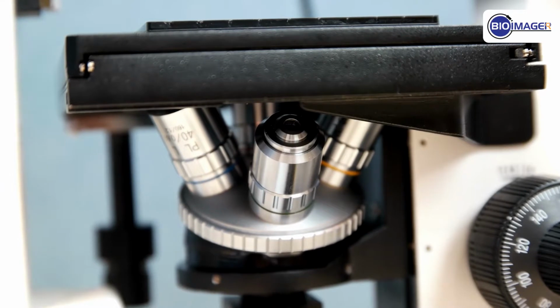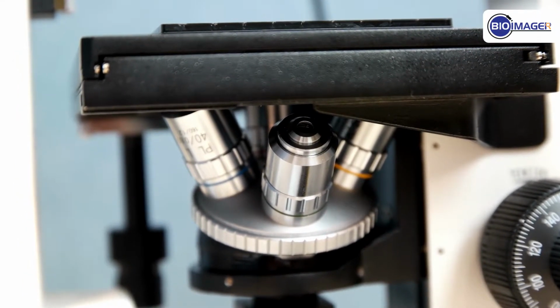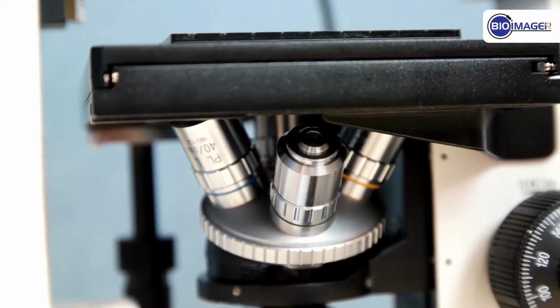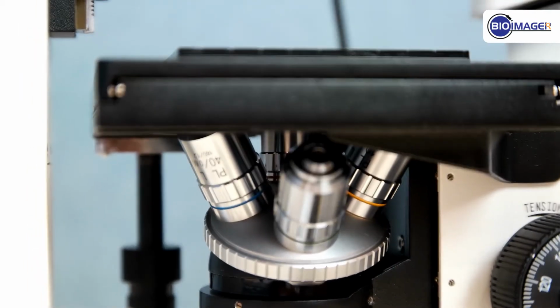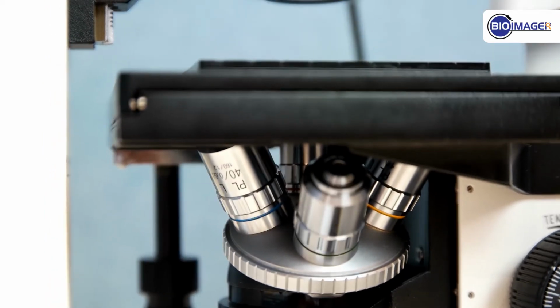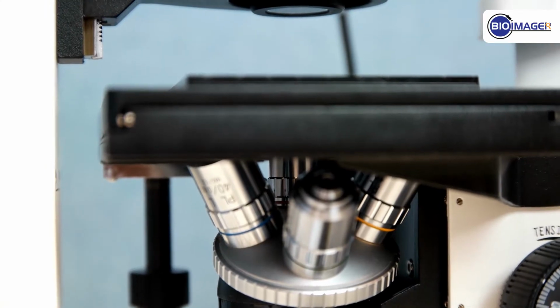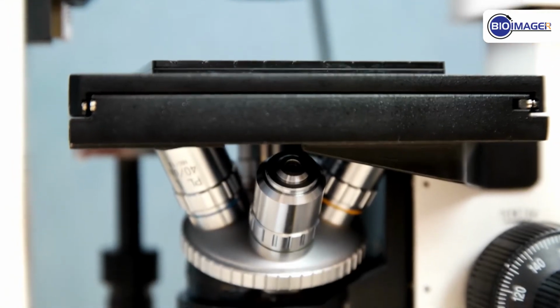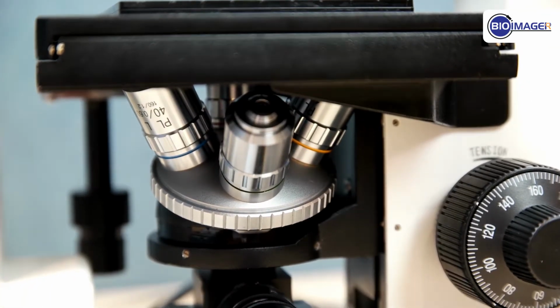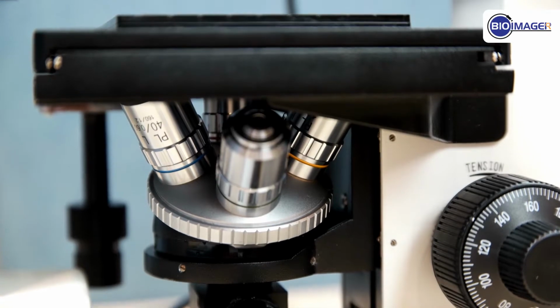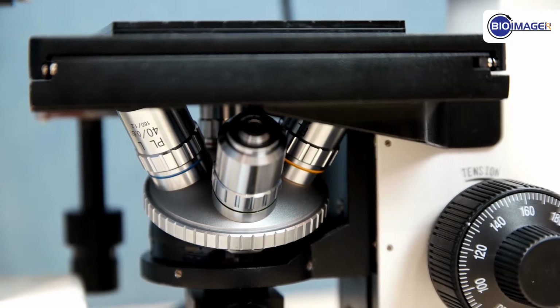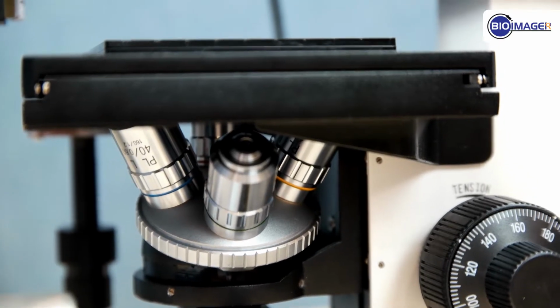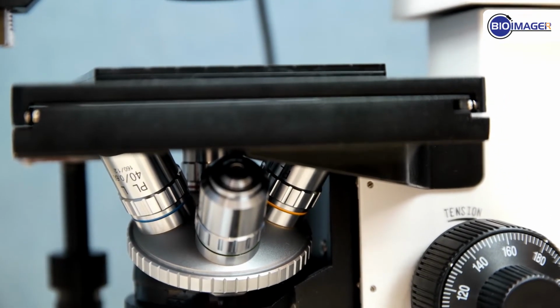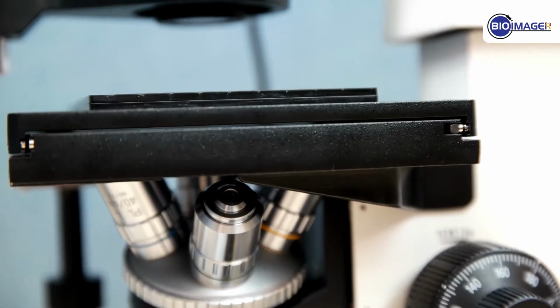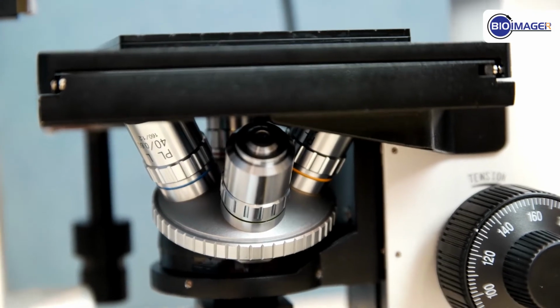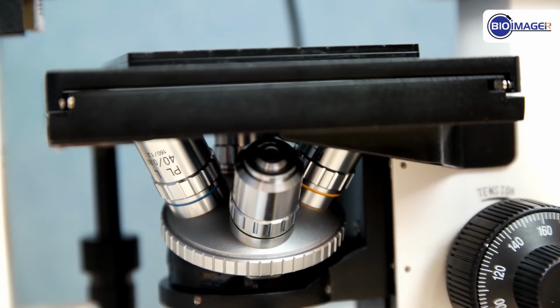This microscope comes with a quadruple nosepiece. It has 4 spots. By default, it includes 10x, 25x, and 40x objective lenses. These lenses can be bright field only, bright field and fluorescence, or bright field and phase contrast, or you can add dark field as well. As an option, several other objective lenses can be added to this microscope. At the low end, you can choose 2x, 4x, 5x, and depending on the application, you may choose different working distances or numerical apertures of lenses such as 10, 20, 25, 40, 50, 60, 80, 100, and even 150x. Starting from 40x, you can select dry, oil immersion, or water immersion lenses.